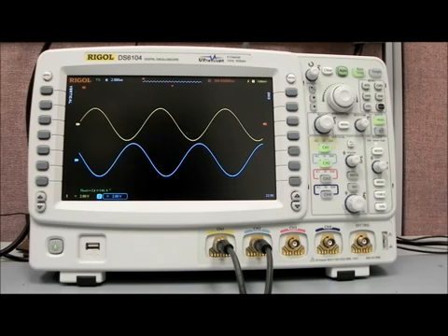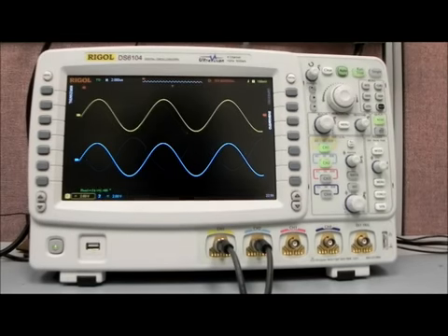So you can also use the automated measurement capability of the instrument, of the DS6000, in order to make those phase measurements between channels, which can be extremely useful as well. And quite a bit faster, I think, but the Lissajous curves, or the X versus Y mode, can also be helpful. And now I'd like to take a closer look at one more feature actually, the display persistence on the DS6000 before we wrap this up.